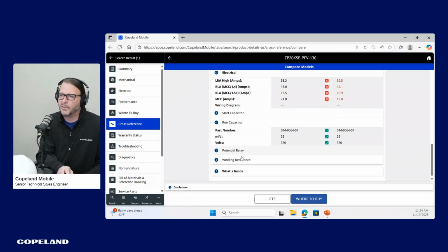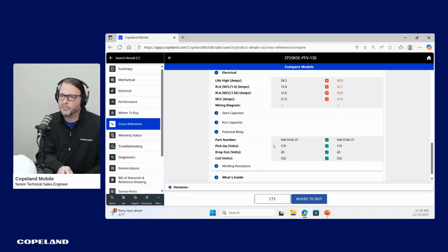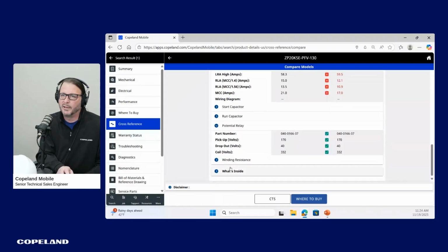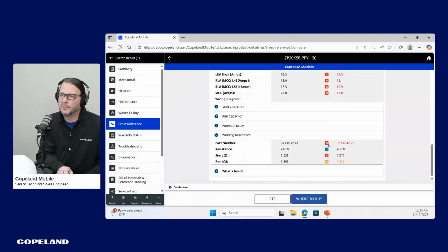Run caps look the same. If you were to use a start cap, obviously you need a relay to bring it in and out, and you've got that. Finally, the winding resistance is slightly different, so if I were to troubleshoot this new model in the future, I'd be keyed in there to know I'm looking at a different winding resistance here.